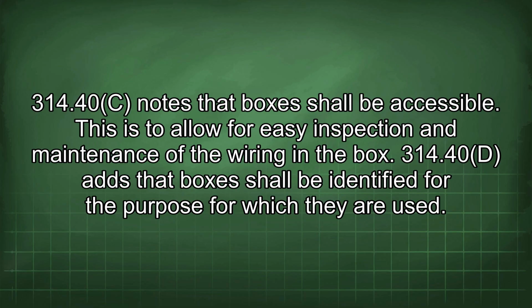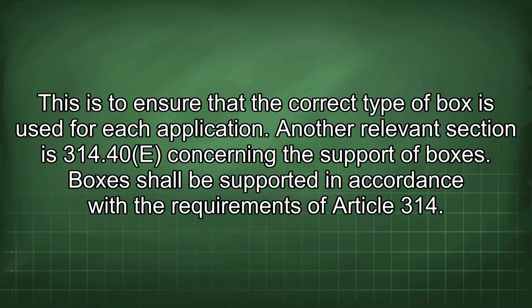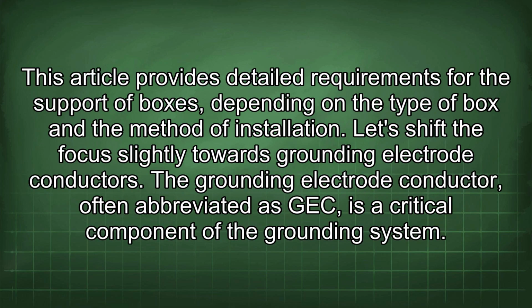314.40(c) notes that boxes shall be accessible. This is to allow for easy inspection and maintenance of the wiring in the box. 314.40(d) adds that boxes shall be identified for the purpose for which they are used. This is to ensure that the correct type of box is used for each application. Another relevant section is 314.40(e) concerning the support of boxes. Boxes shall be supported in accordance with the requirements of Article 314. This article provides detailed requirements for the support of boxes, depending on the type of box and the method of installation.